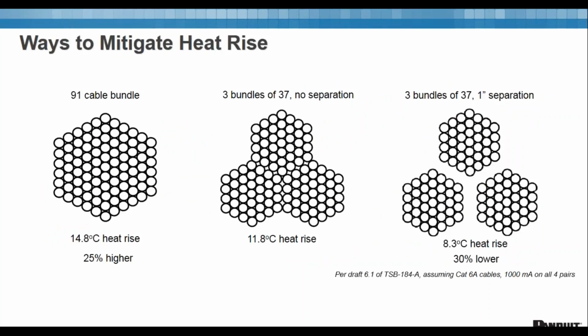Some ways to mitigate heat rise, and this is taken out of the TSB-184 draft, is by separating your bundles. So take the one in the center where you've got 3 tightly packed bundles of 37, no separation. That would be at about 11.8 degree heat rise. Now, if that's a full 91 cable bundle, that's 25% higher at about 14.8. Now, if you've got 3 bundles with a 1-inch separation, that's about 30% lower, or about 8.3 degrees heat rise. So if you are concerned about it, if you make the bundles smaller and add a little bit of separation between them, it does help a lot.